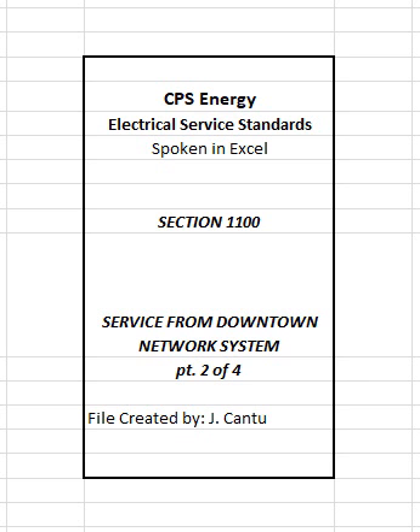5. Ventilation openings shall be covered with durable gratings, heavy gauge screens or louvers, according to the treatment required in order to avoid unsafe conditions. Gratings, etc. used to cover the openings shall be in accordance with CPS Energy specifications and shall be furnished and installed by customer. 6. Ventilation ducts shall be constructed of heavy gauge corrugated steel or concrete and all joints shall be watertight. 7. Ventilation indoors will not be accepted by CPS Energy.